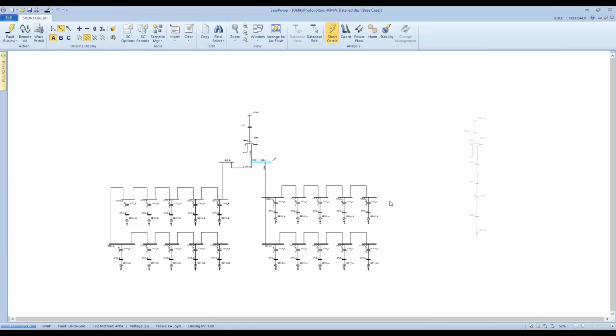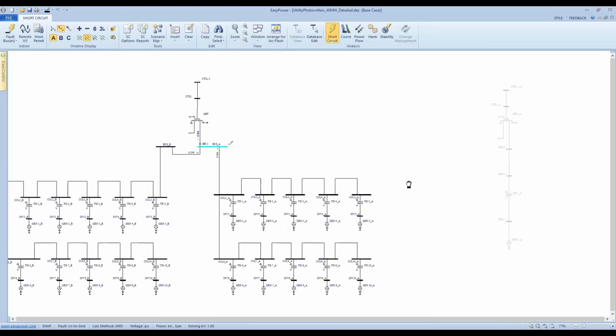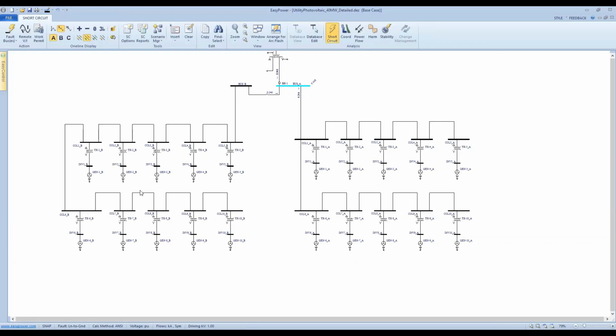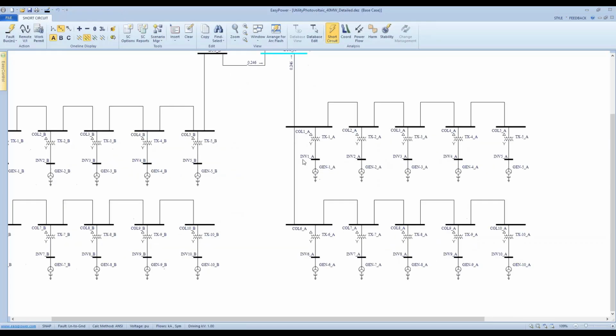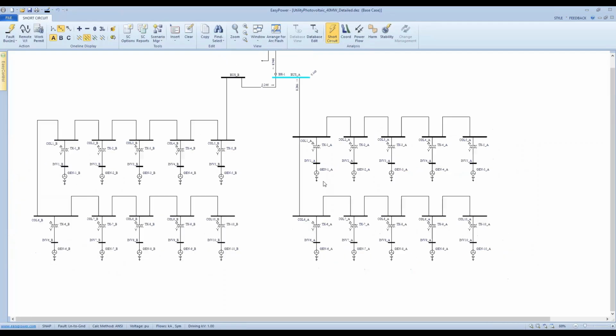inverters in your plant. This is too ideal, that you have the same inverter in your plant. In your actual design, you may have a couple of different inverters. Let's say you may have different inverters for inverter 1 to inverter 5. Let's say you may have a 4 megawatt. What are you going to do? You have a different inverter, you have a different GSU. What are you going to do with that?